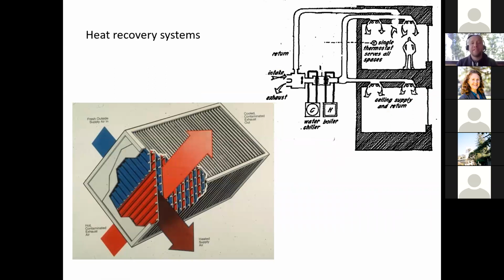Here's a kind of a blow up of that system so you can start to see some of those air channels in each direction. So again, the air streams never touch, but they pass right by each other. And this is a really great strategy on all air systems. So Gail last week talked about VAV systems, variable air volume, and constant air volume systems, CAVs. Those all have some portion of air that's always getting exhausted out of the building. And so adding a heat recovery ventilator section or heat core, if you will, to that section can really increase the efficiency of the building, especially in more extreme climates.